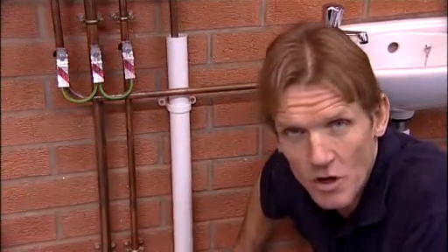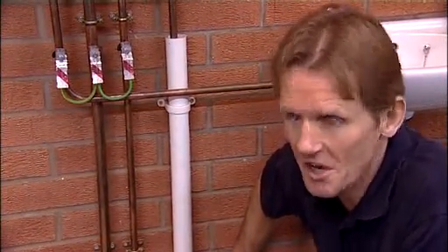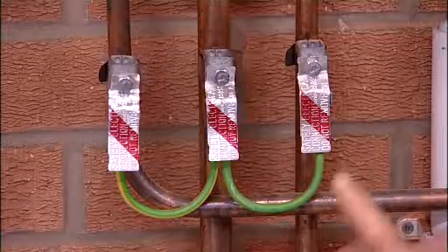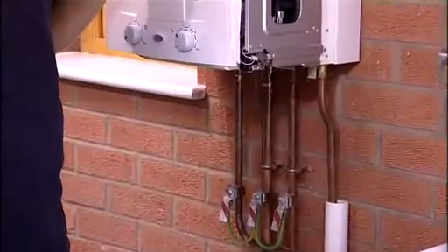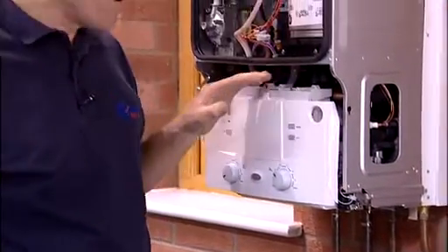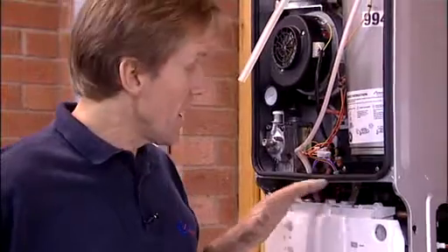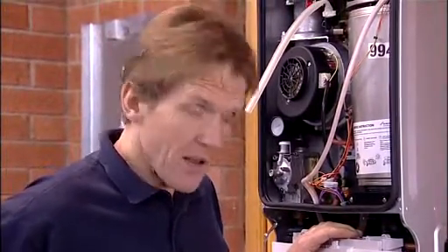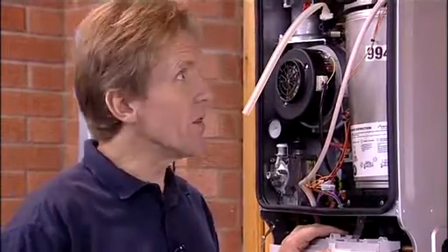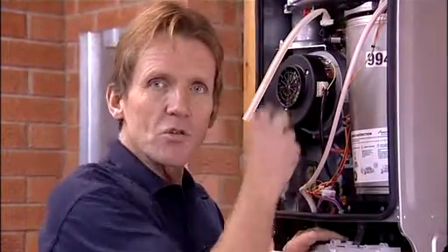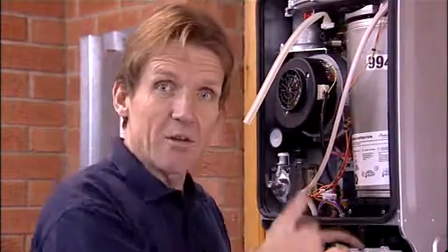Earth bonding is an essential safety requirement, and of course nobody wants to see it above their worktop, but it must be visible, and of course if you do it properly, it can also be very neat. Bosch boilers have been carefully designed to try and protect the internal PCB and controls from water damage. Now the fact that the pipework is connected underneath the boiler helps an awful lot, but if you're going to run the pipework up behind the boiler, make sure that you don't have vulnerable connections made just above the boiler, which might cause a leak down inside the boiler, because that kind of damage can be very expensive to repair.